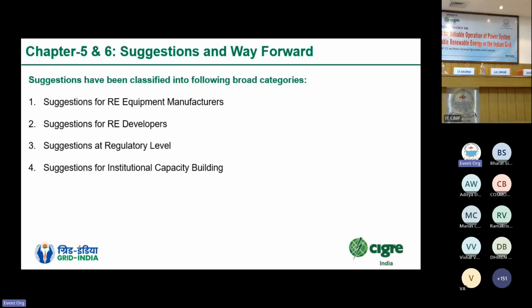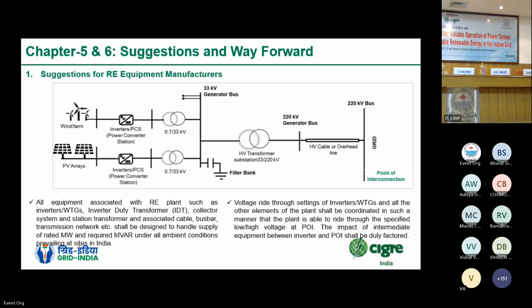Suggestions are there for RE equipment manufacturers. Suggestions are there for RE developers. Suggestions are there at the regulatory level to enhance and update the standards with the increasing RE penetration. And suggestions are there for institutional capacity building of the stakeholders. Starting with the suggestions, the first suggestion is that all equipment associated with the RE plant, such as inverters, WTGs, IDTs, collector system, station transformer and associated cable and bus bar, should be designed to handle supply of rated active and reactive power under all ambient conditions prevailing at sites. So the RE developers shall ensure that all their equipment is able to withstand and display the desired performance under all sets of ambient conditions, and that no equipment causes any hindrance in displaying the desired performance.